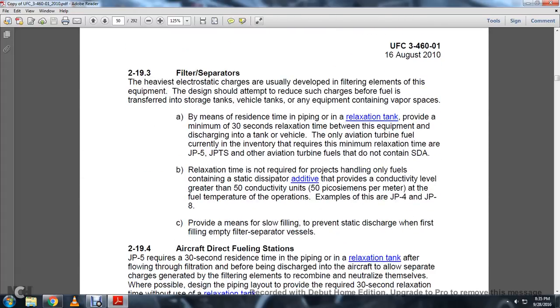219 Filter separator. The heaviest electrostatic charges are usually developed in the filtering elements of the equipment. Design the equipment for the charge to be dissipated, reducing such charge before the fuel is transferred into storage tanks, vehicle tanks, and equipment containing the vapor spaces, by means of residence time in the piping and a relaxation tank provided with a minimum of 30 seconds relaxation.